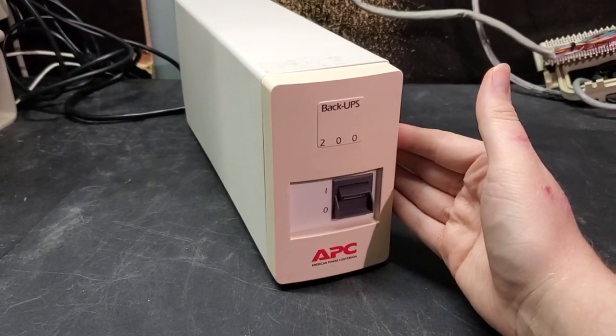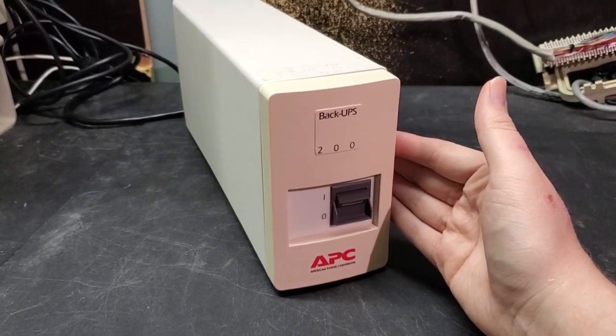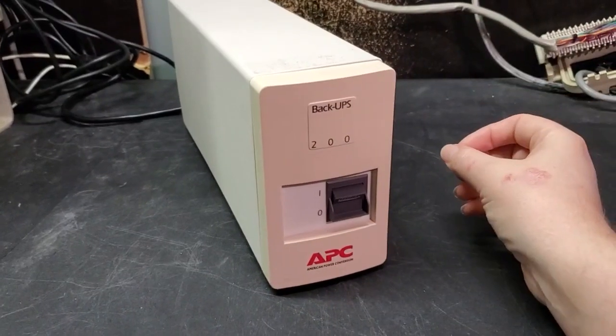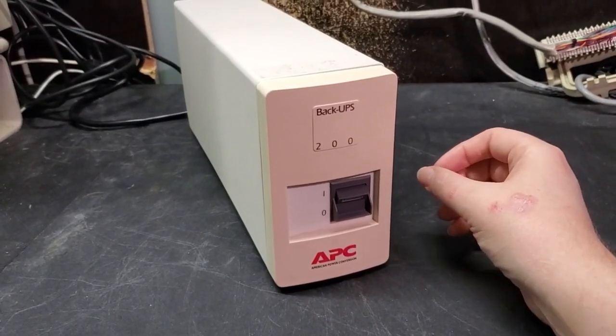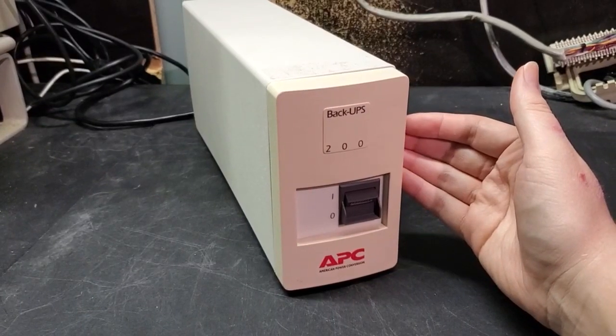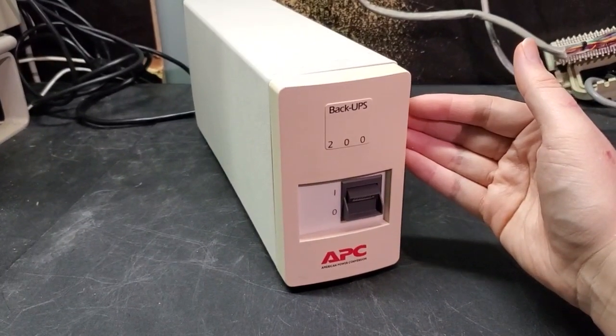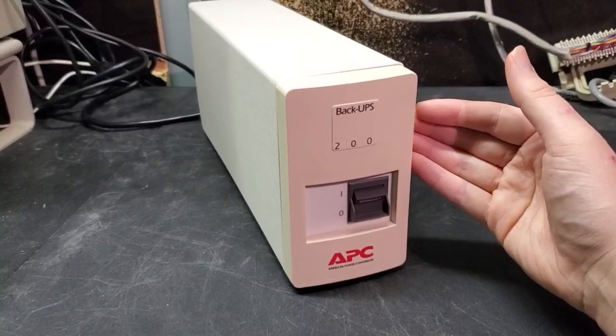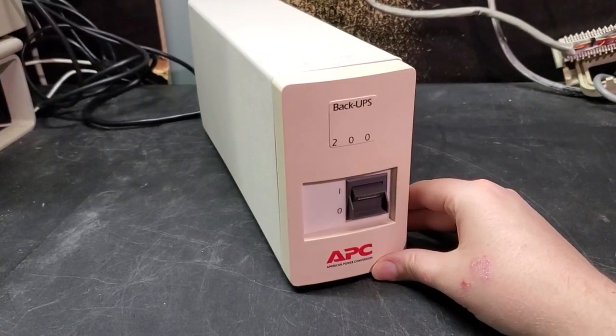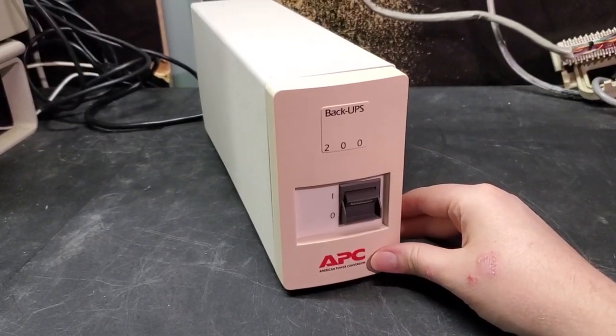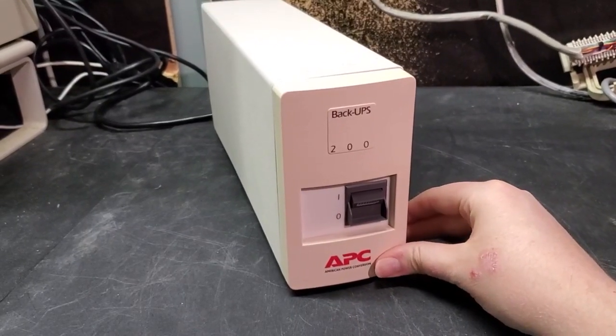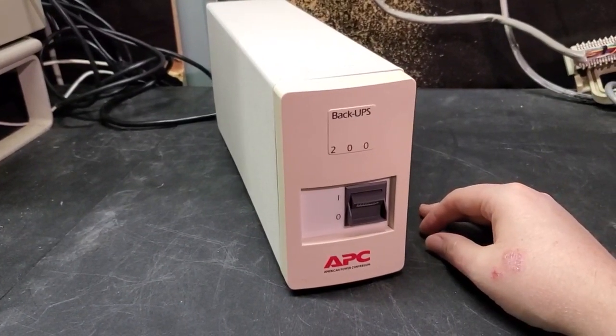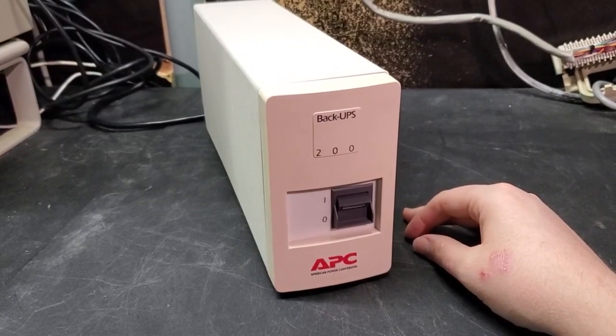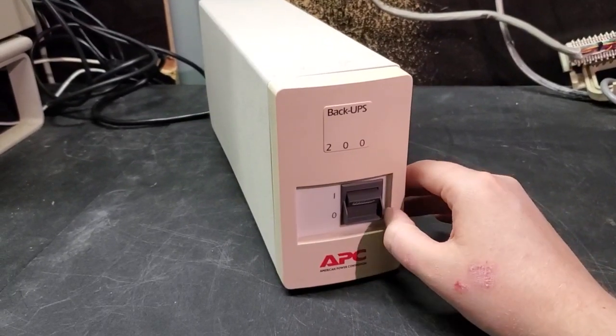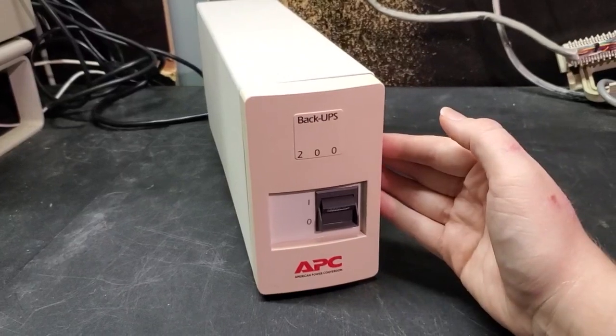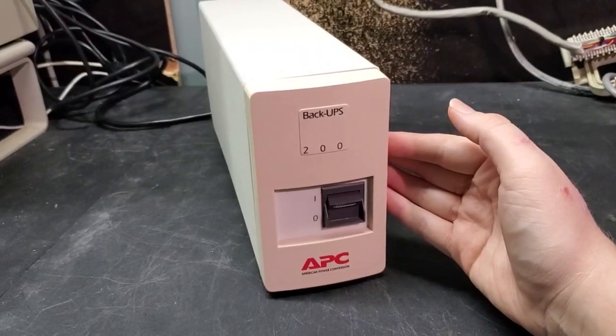There's no fan in here, for example, so when you subvert the original design intention by sticking in a battery that's double the capacity—able to keep it running for double the amount of time—you've got to be careful, because APC always designed, and to this day designs, their UPS to be able to run for 5 minutes at a full load. That's how much battery power they put in: enough to run a full rated load for 5 minutes.